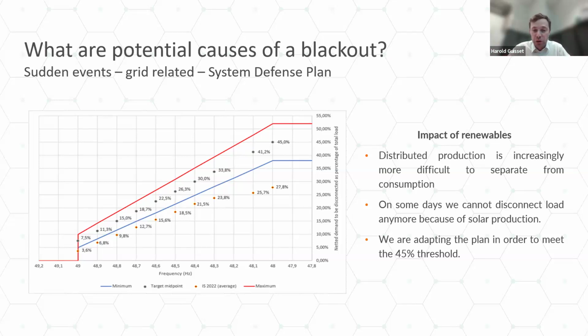And what we see, of course, and I think you all know that, is that more and more solar is produced at distribution level. And when Elia disconnects a full substation, it is possible that the substation was actually feeding electricity, because so much solar was being produced that the substation was feeding into the Elia grid. And if we disconnect that substation at the wrong moment, we are actually disconnecting production and not consumption. So we need to adapt that plan. We need to evolve together with the energy transition. And that is where Thomas will explain what we're doing to solve this issue.